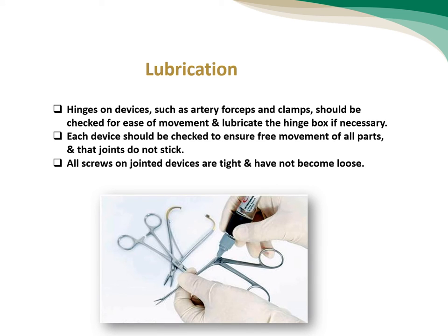Lubrication is very important. Lubricate the hinges on devices such as artery forceps and clamps. They should be checked for easy movement, and the hinge boxes lubricated if necessary. Each device should be checked to ensure free movement of all its parts and that the joints do not stick. All screws on jointed devices should be tight and not have become loosened with time. Okay.